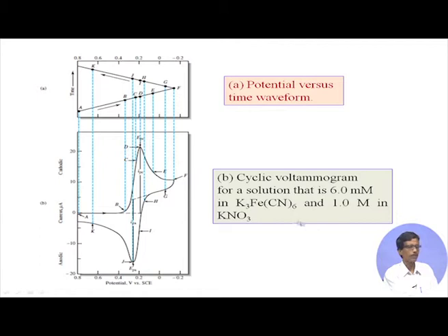All this information is related to a very electroactive species, because ferricyanide is a standard reference material. Once an instrument is installed, if you install a new instrument, the first thing your engineer will ask you is to give some amount of reference material. This material is available in any lab, any school lab, college lab, university lab or any other institutional lab. Ferricyanide is a cheap molecule. So, this is your standard material. There is no need to have any costly material to standardize that thing.